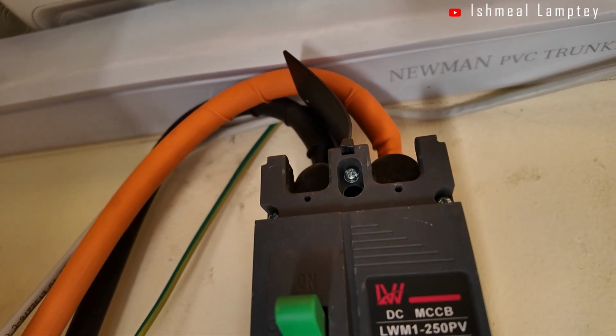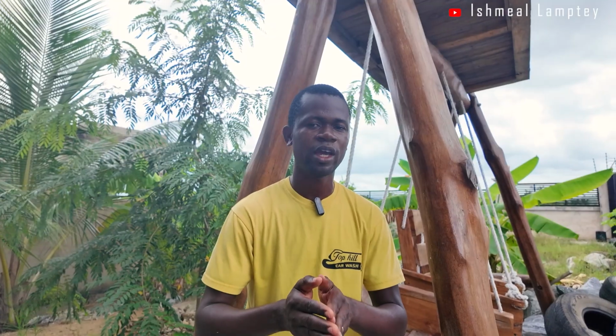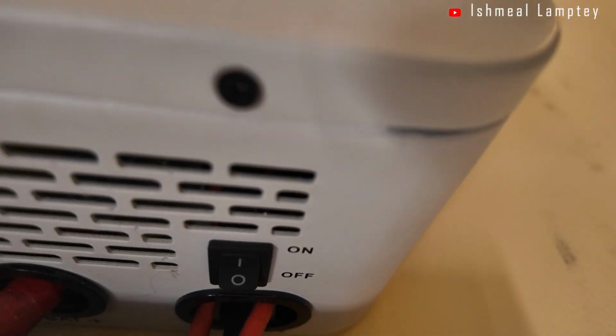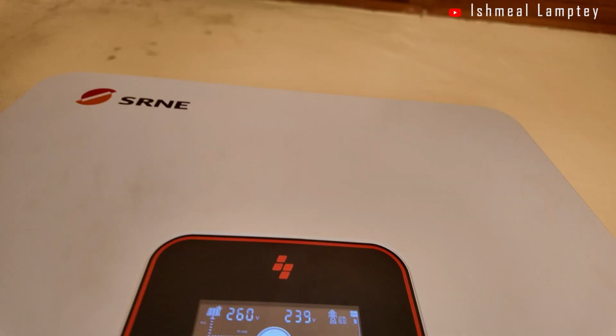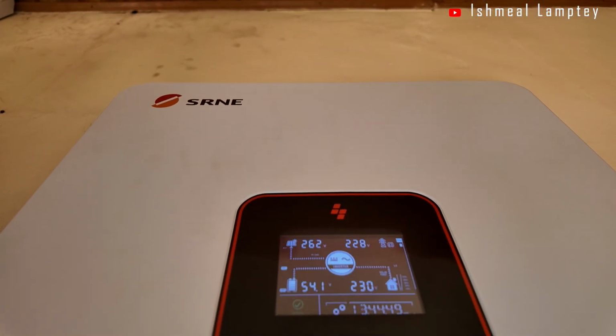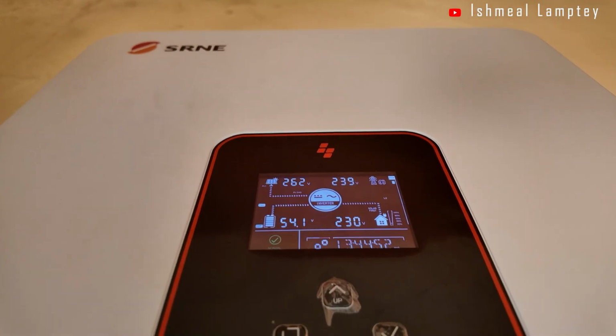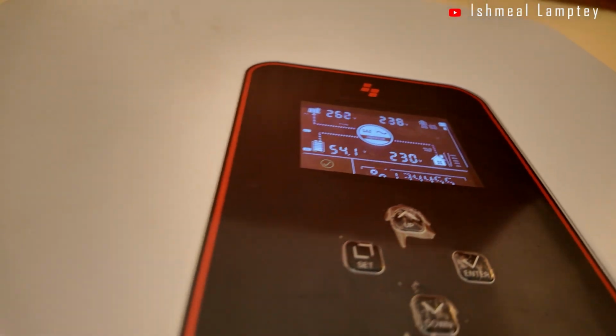So upon doing all these configurations, it was time to do the configuration on the system itself, where you specify how you want the system to function. As part of the configuration, you're able to select what does what at what point of the day. At this point, you have the panels, you have the battery, you also have the grid. So how do you want to use it? What we did was make the panels the first priority in terms of power provided to the house. First priority in the sense that during the daytime, where there's daylight and a lot of sunlight, that is going to serve power to the load. And because of the size of panels we had in total, that was able to power a lot of appliances during the daytime. So that was our first option.